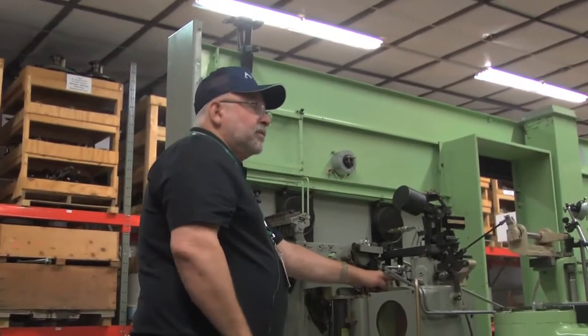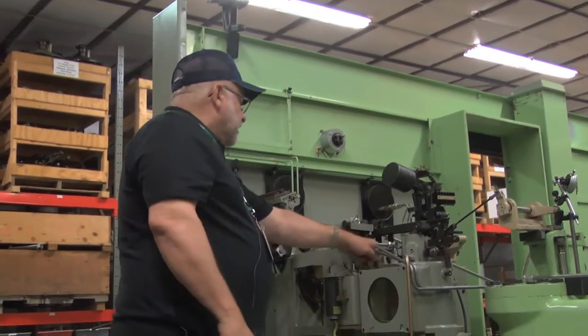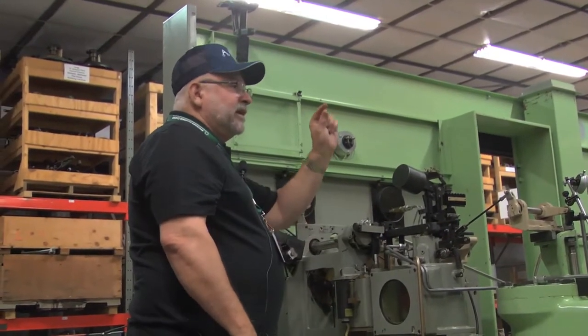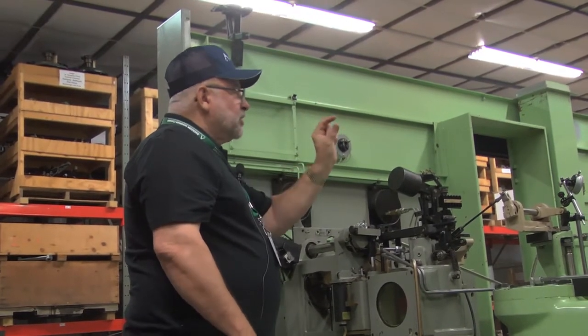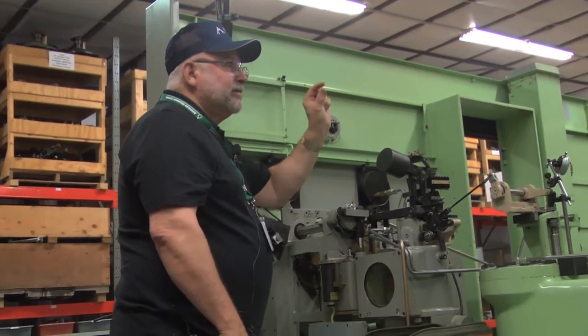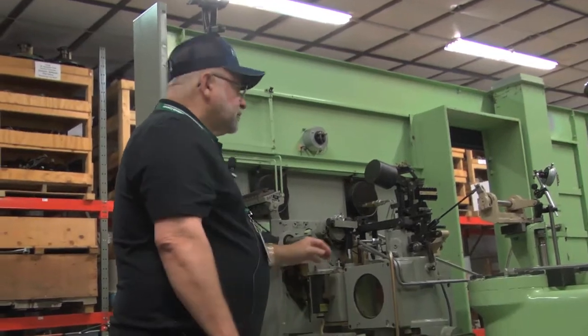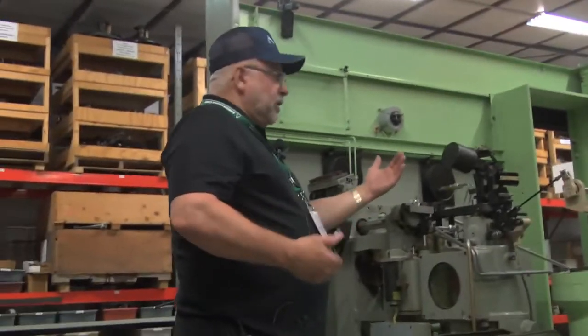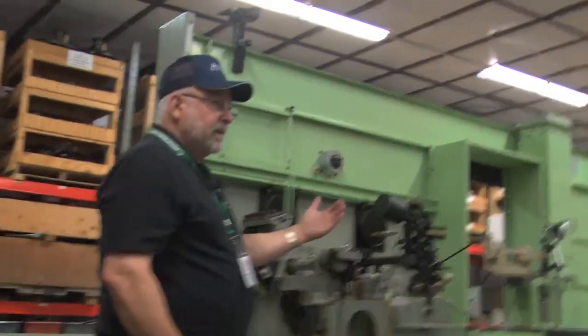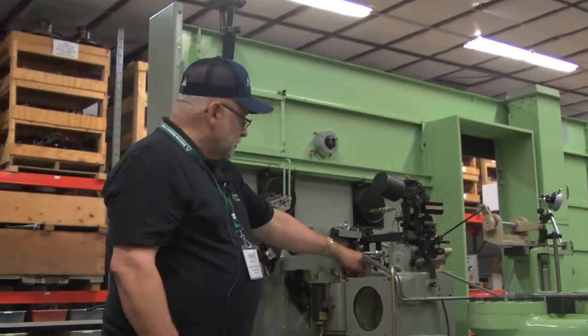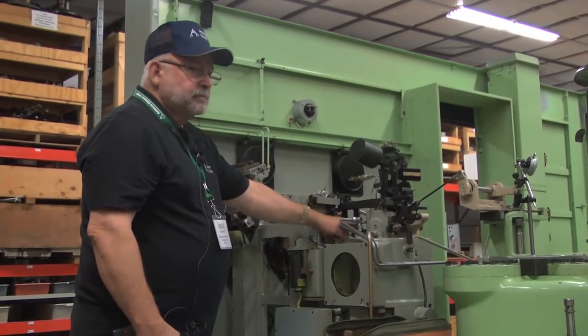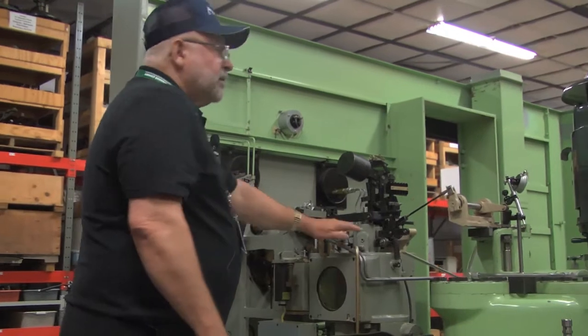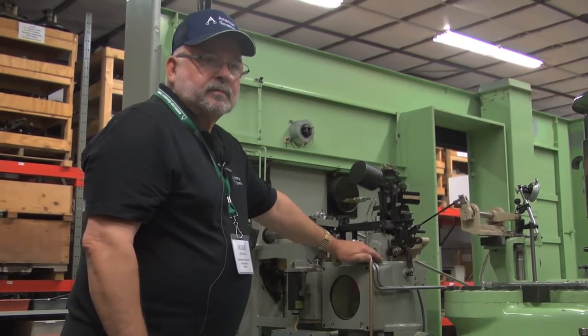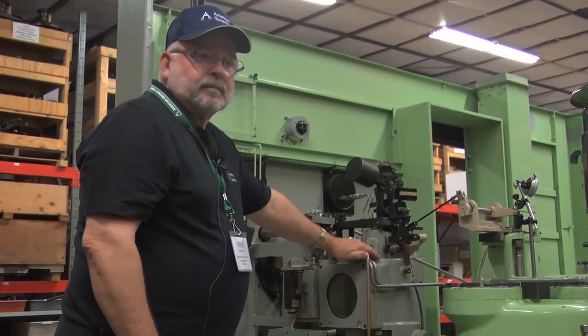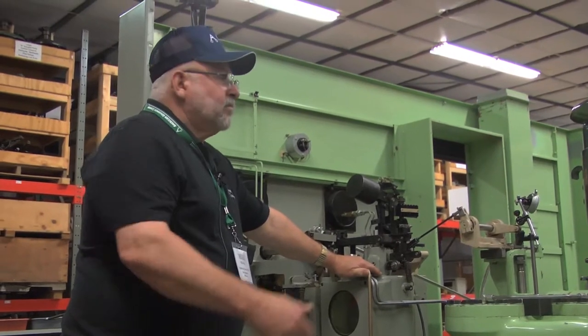I haven't seen that personally on a Pelton. Mine are either square like this, or it just has that little oblong pointer. Right, ours is actually, you have the... And when a unit loads, it goes down. Okay, as the unit loads, this will swing down. The speed adjustments, yeah, and it's really easy because it's just a thumb screw. You just turn it either way. It doesn't even have a lock on it.